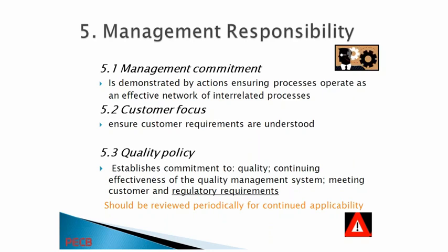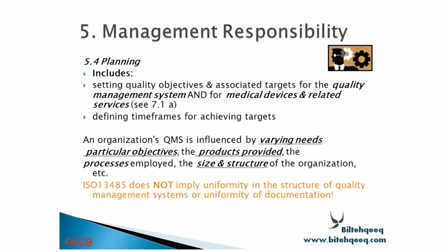Development of the quality policy: the main focus of the quality policy is the fulfillment of the customer requirements as well as the regulatory requirements. And the quality policy should be reviewed periodically for continued applicability. 5.4 is planning, which includes setting quality objectives and associated targets for the quality management system and for medical device related services, and defining a time frame for achieving targets. So we have to plan and set the targets, and we have to describe in what way we will be able to achieve these objectives.